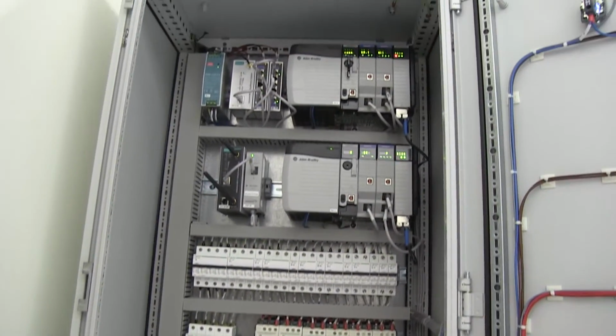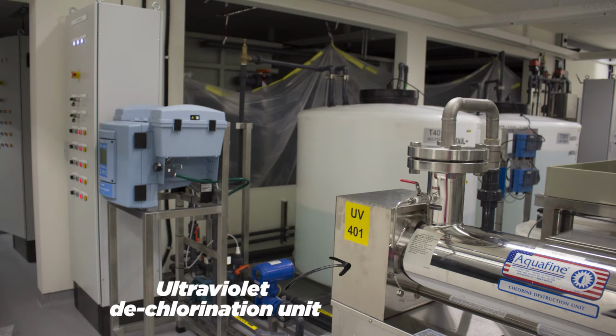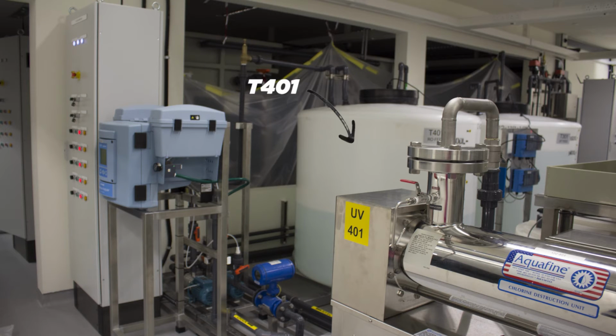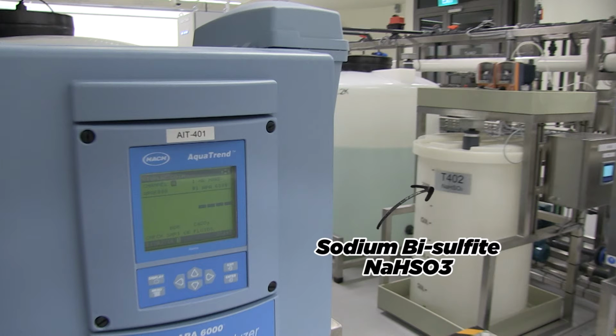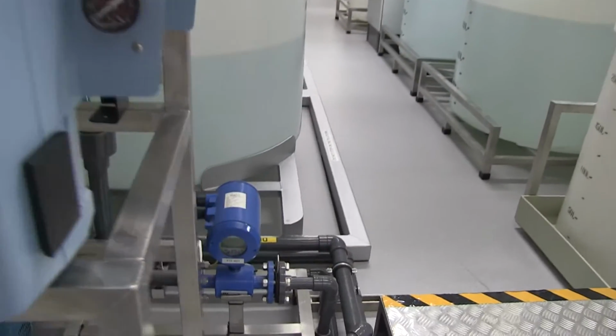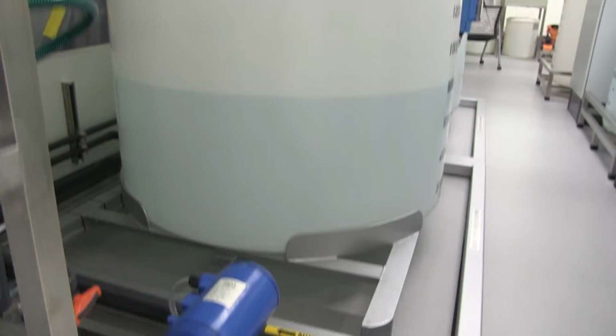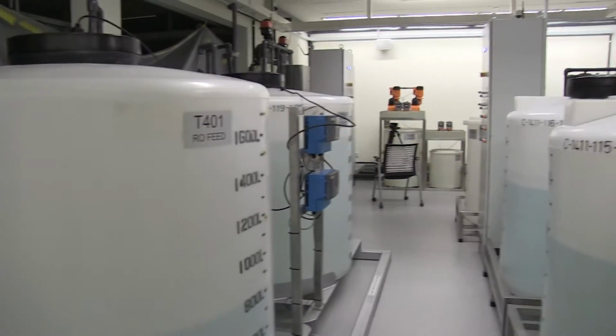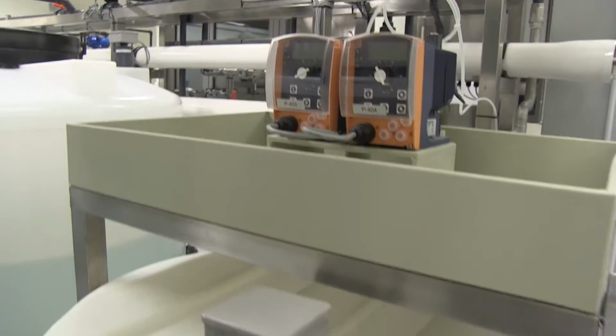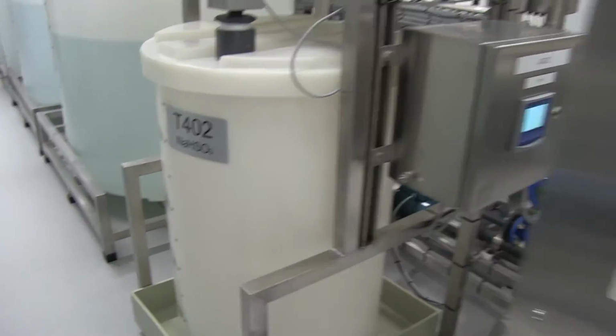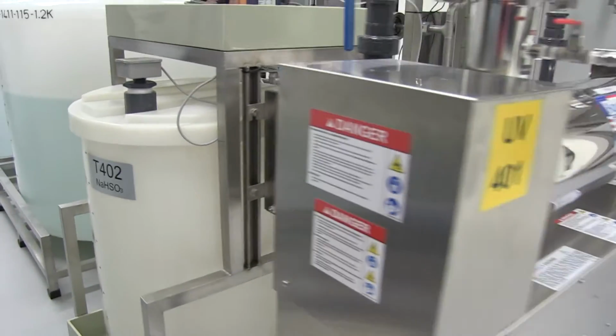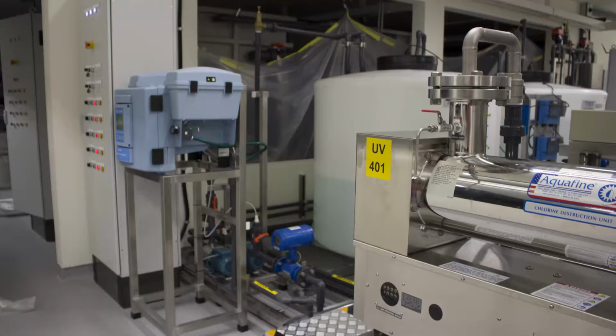Stage 4 is meant for dechlorination of water before it is moved through the reverse osmosis units. This is done to prevent oxidation of membranes in the RO unit. The PLC controls the ultraviolet dechlorination unit to remove free chlorine from the water from tank 401. The controller may also use sodium bisulfite, that is NaHSO3. Dechlorination is necessary to remove free chlorine before water is fed into the reverse osmosis unit. The ORP, which is oxidation reduction potential, monitor is used to measure the absence of chlorine. The dechlorination process reduces free chlorine to harmless chlorides and readies the water for feed to the RO unit.